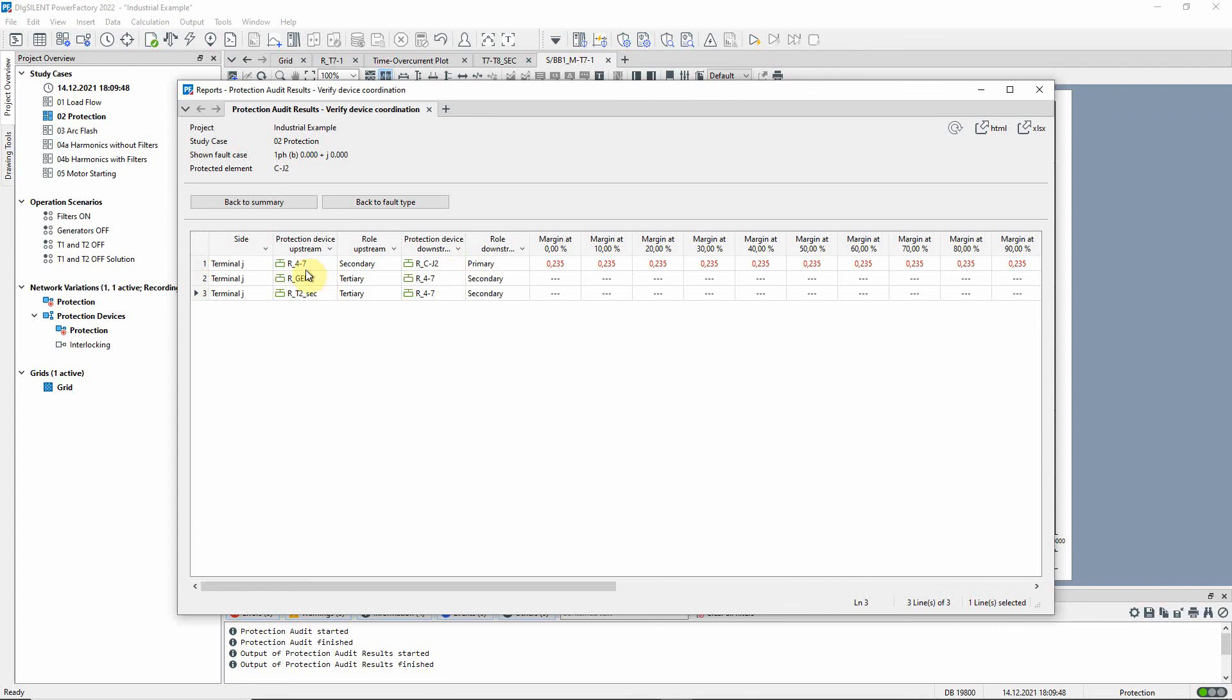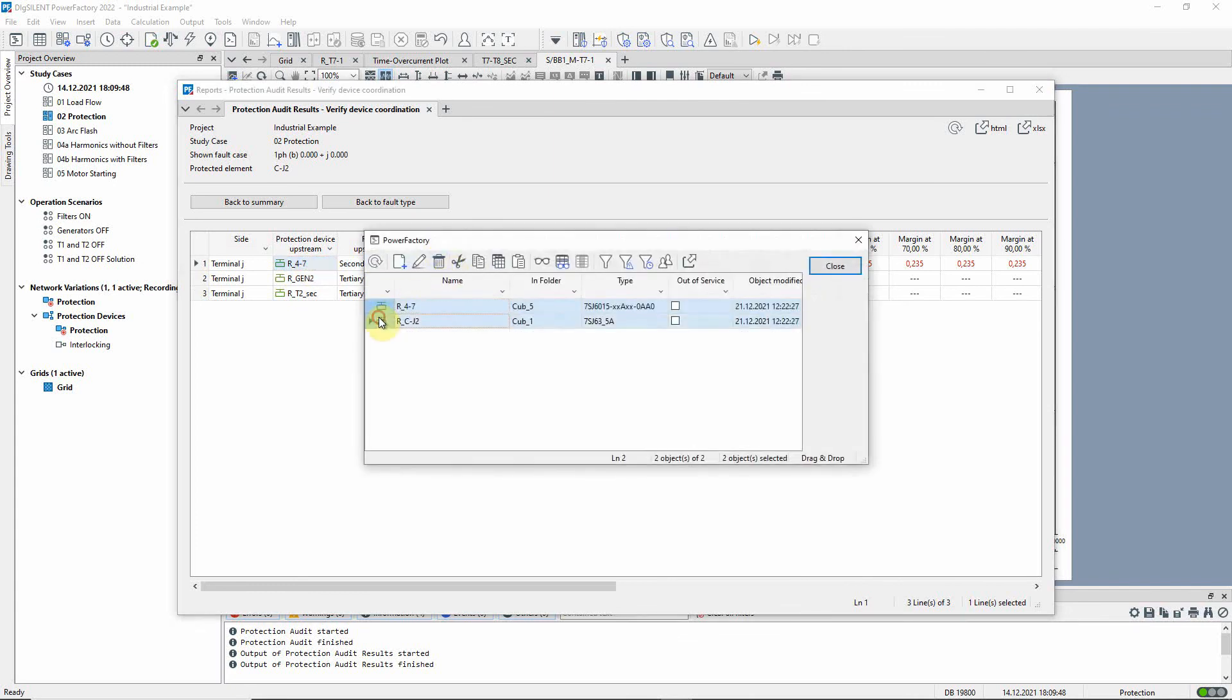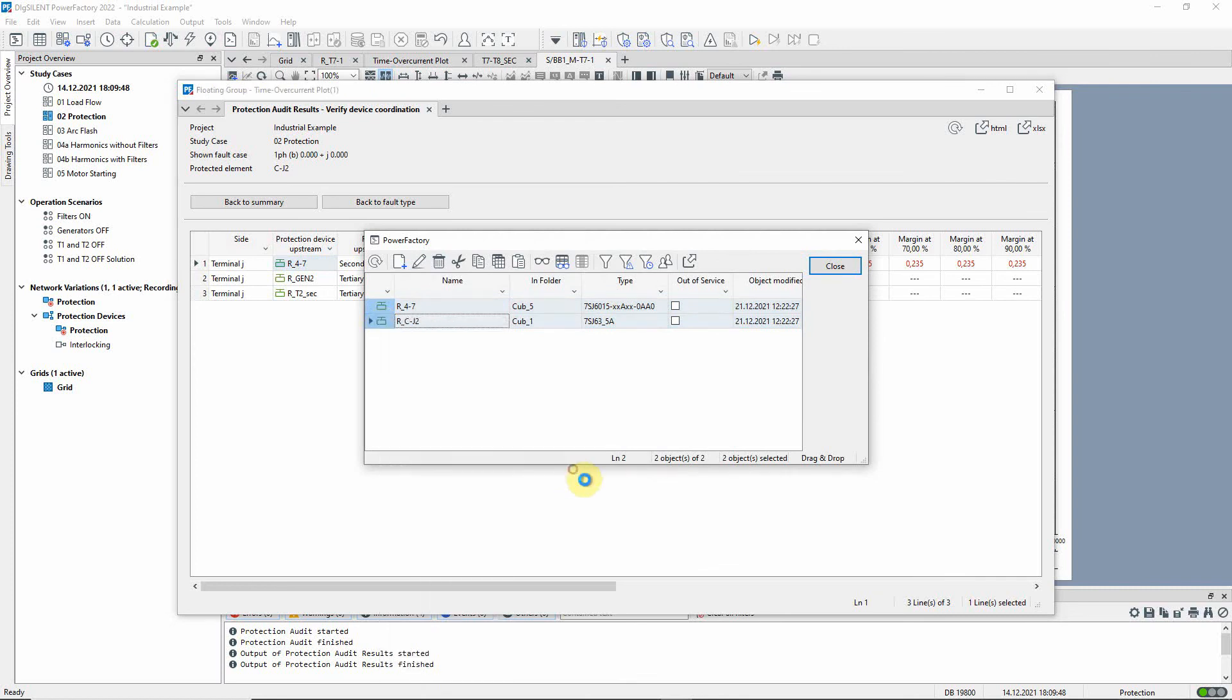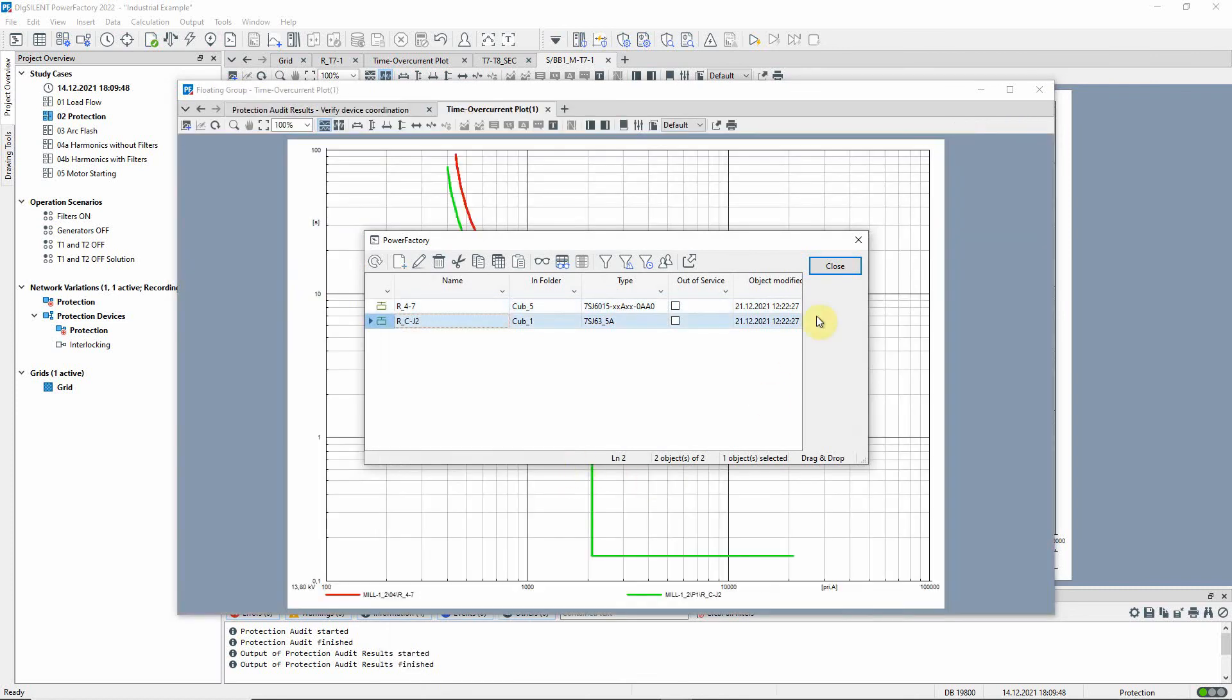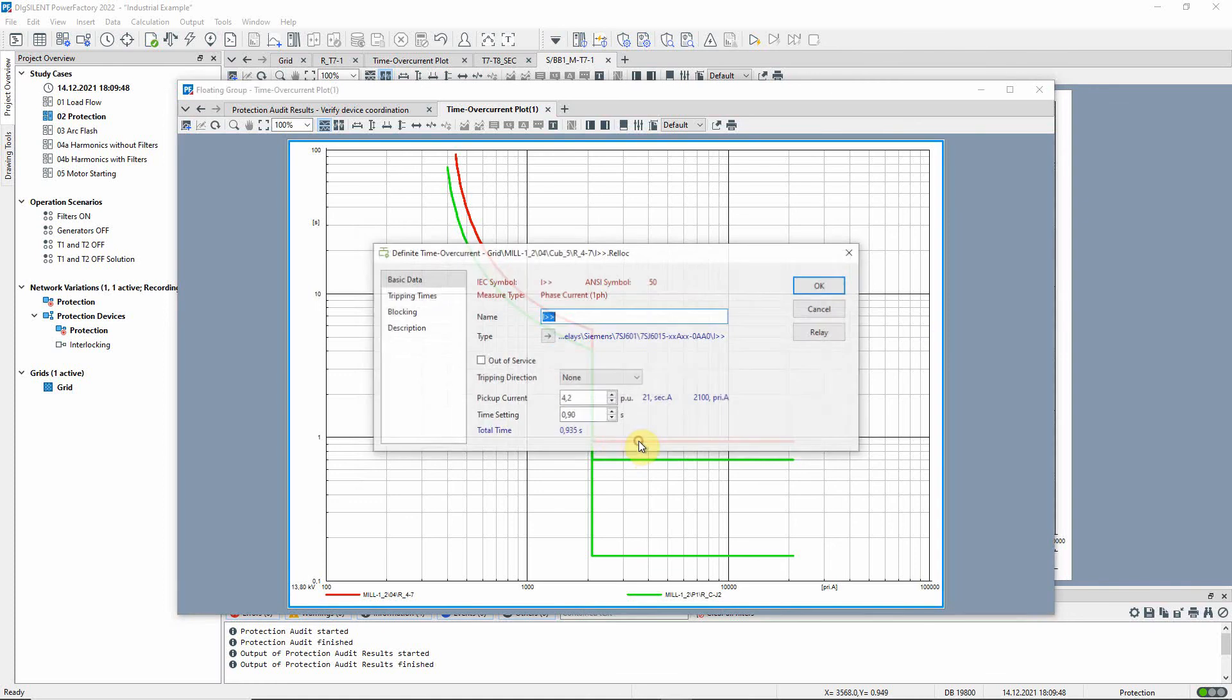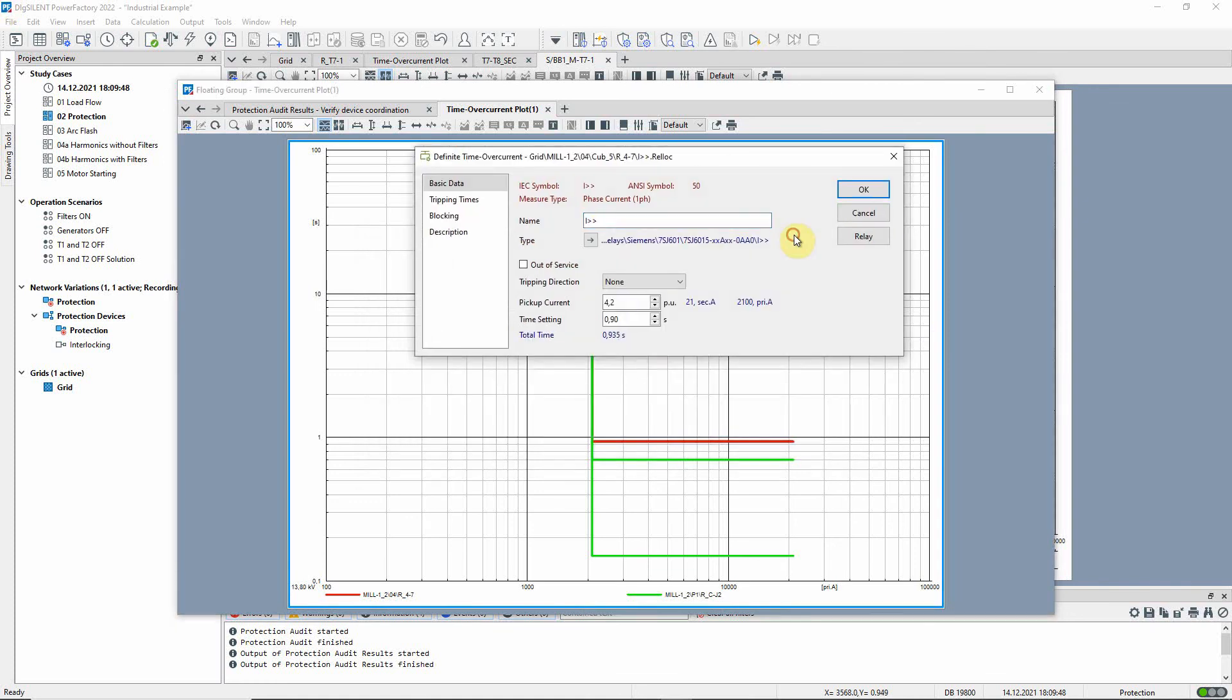Let us show a time over current plot for these relays. We can see the gap of 0.235 seconds between these two curves. If we increase the time setting on this relay a little, the time delay between the two relays will be increased above the threshold of 0.25 seconds.